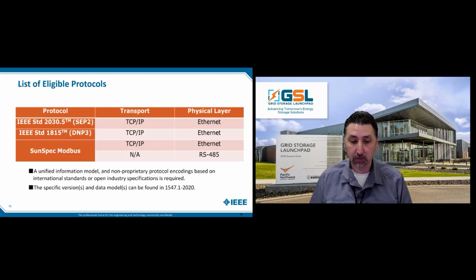It's important to note this because 1815 is one of these protocols which is just kind of like registers. You just put things in a register and read and write, without having the semantics that you need associated with those points - voltage, for instance, or phase one voltage, to be more specific. You may have phase two voltage on a port, read it as phase one. So you need this semantic interoperability. 1815 by itself does not have that.